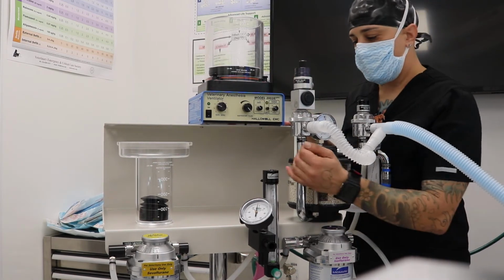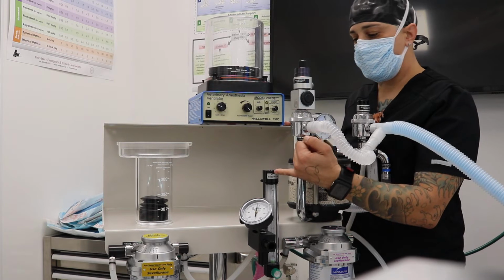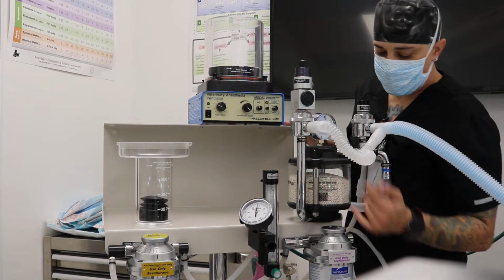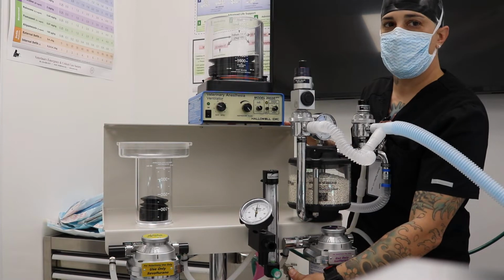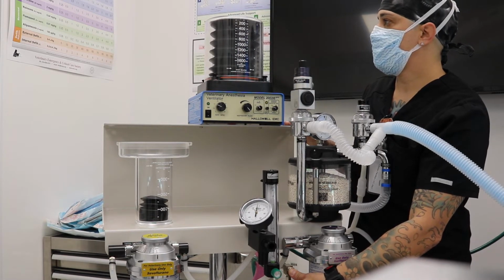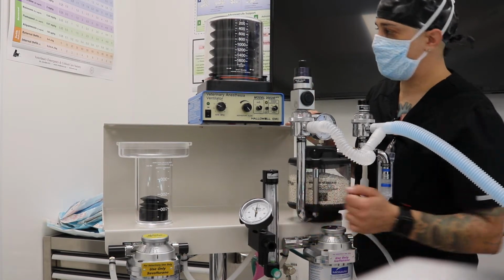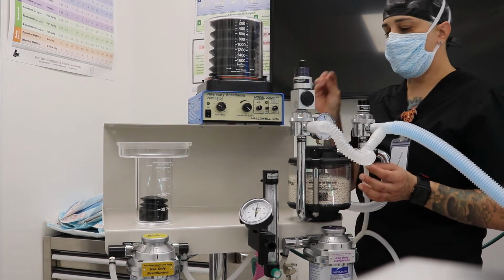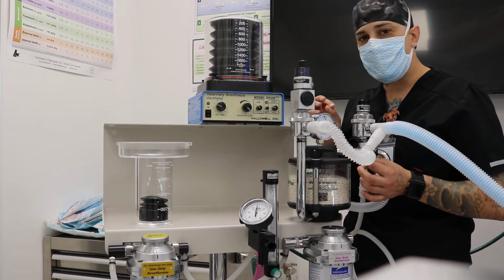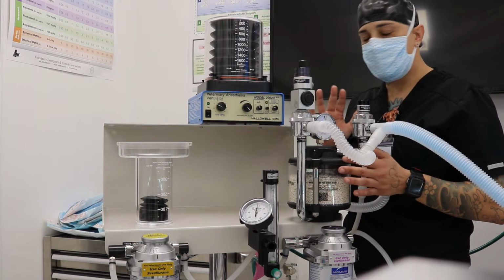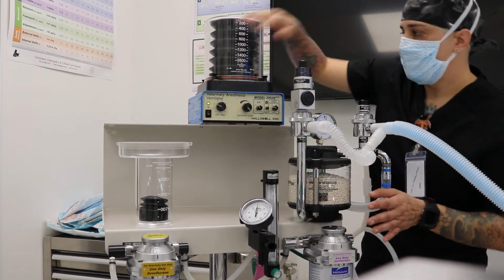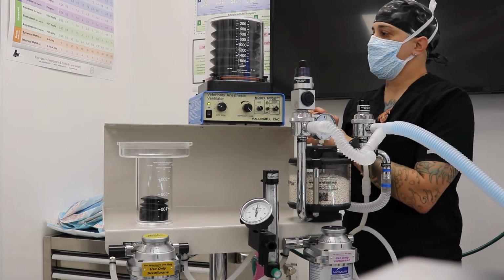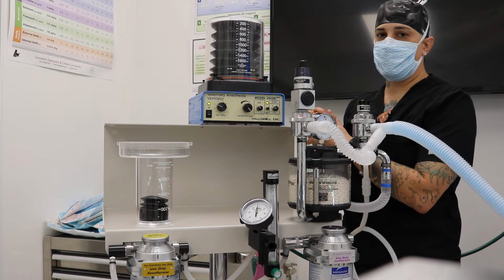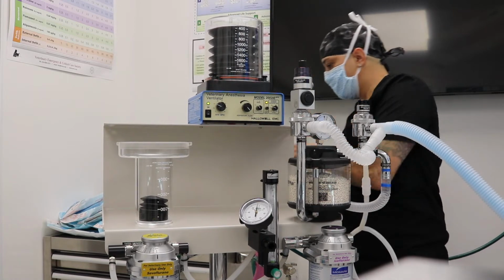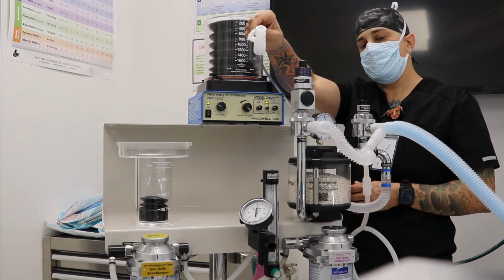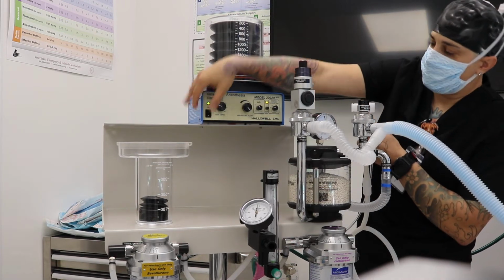Muy importante, never have your oxygen on. Your oxygen will mask a leak. So we are just going to flush our valve here to fill our bellow. Okay, so it's full. You can see oxygen is still off. I'm just going to turn it on. You're going to hear a screaming sound that is going to make you panic. But don't panic. This is what you're going to learn. Okay, on. That is the sound that you will hear when your pressure transducer is not connected. So, go ahead and turn this off.